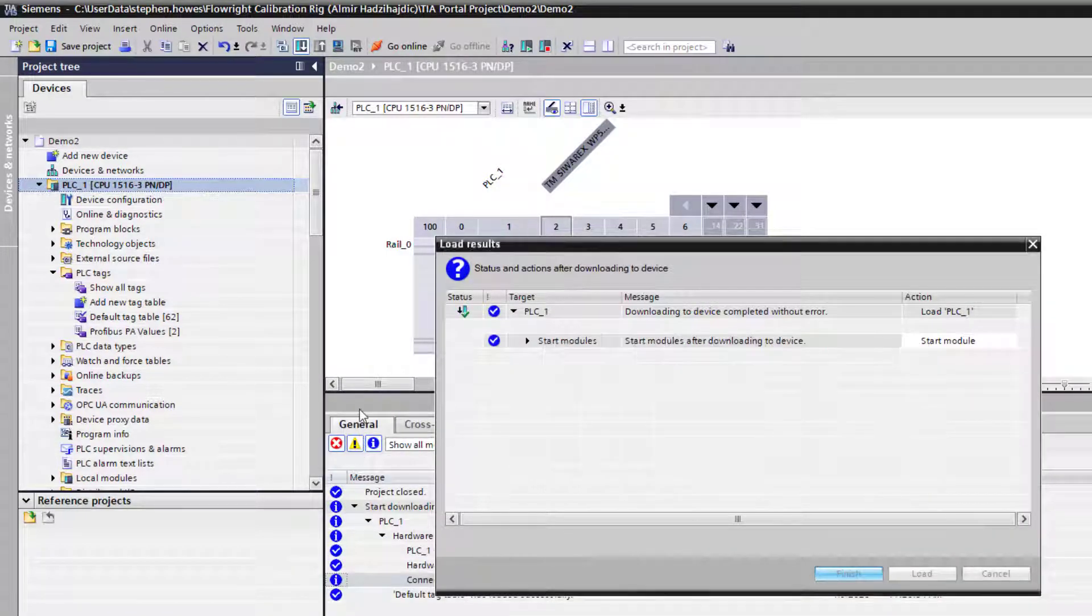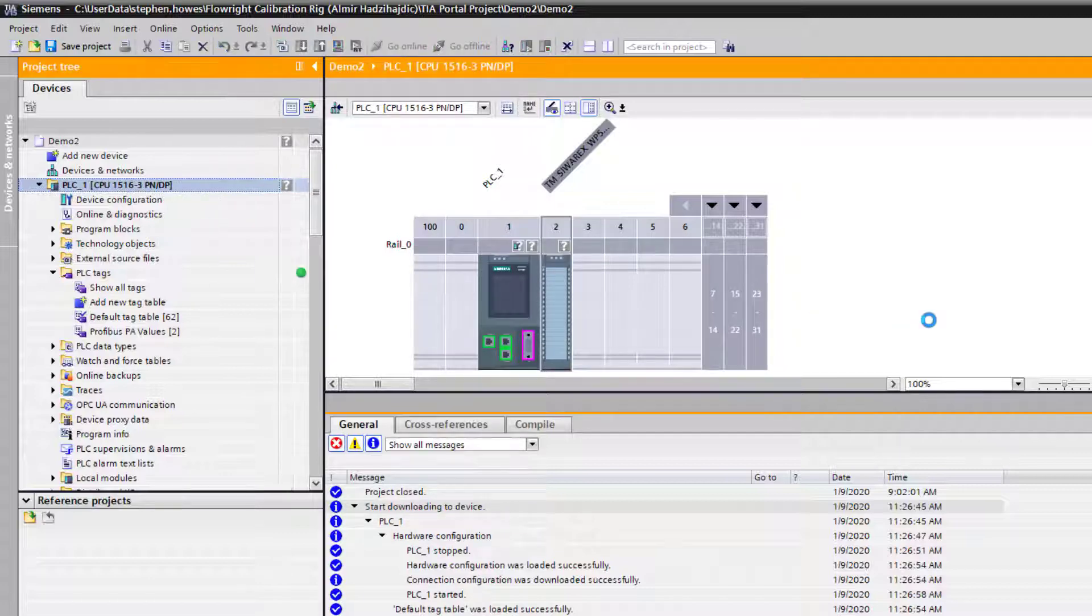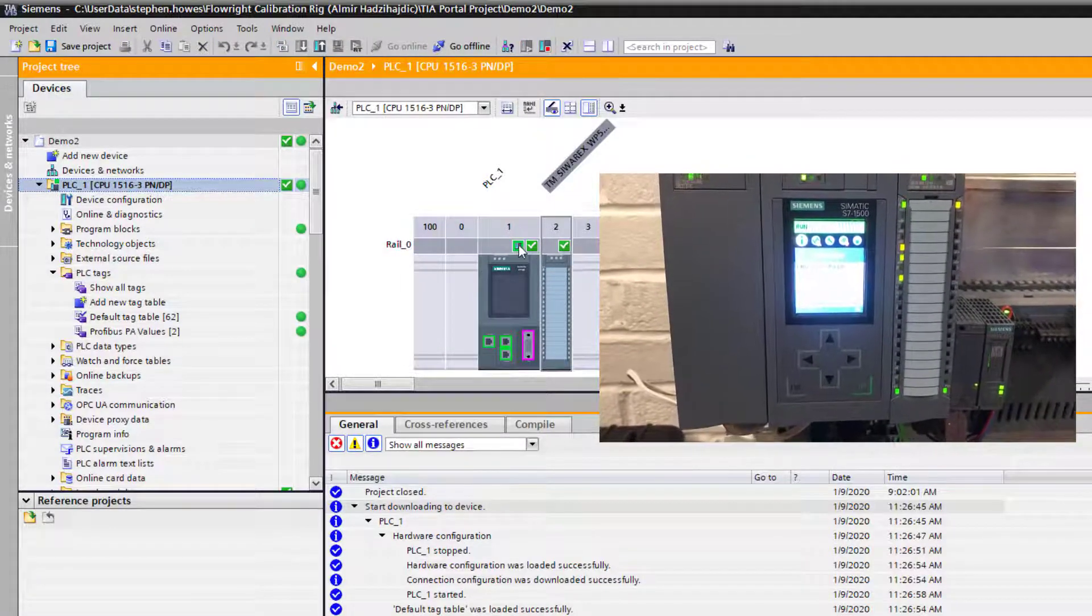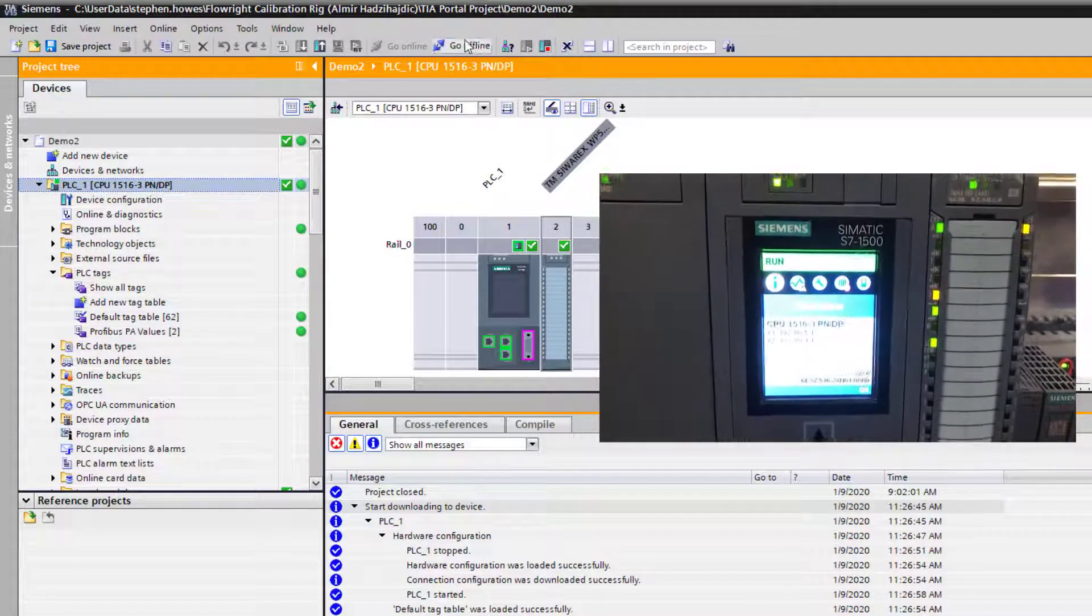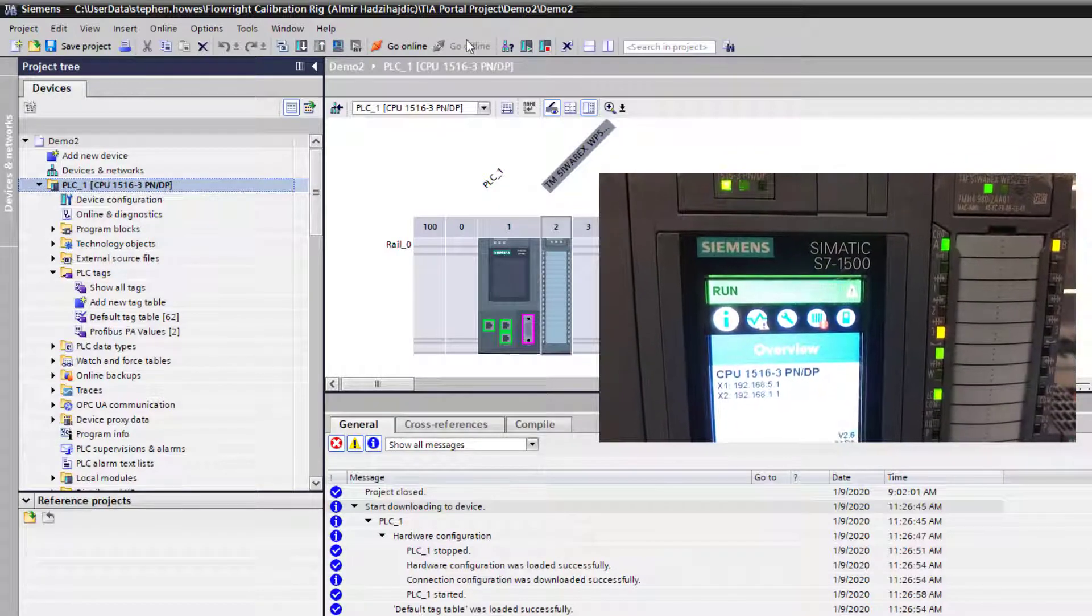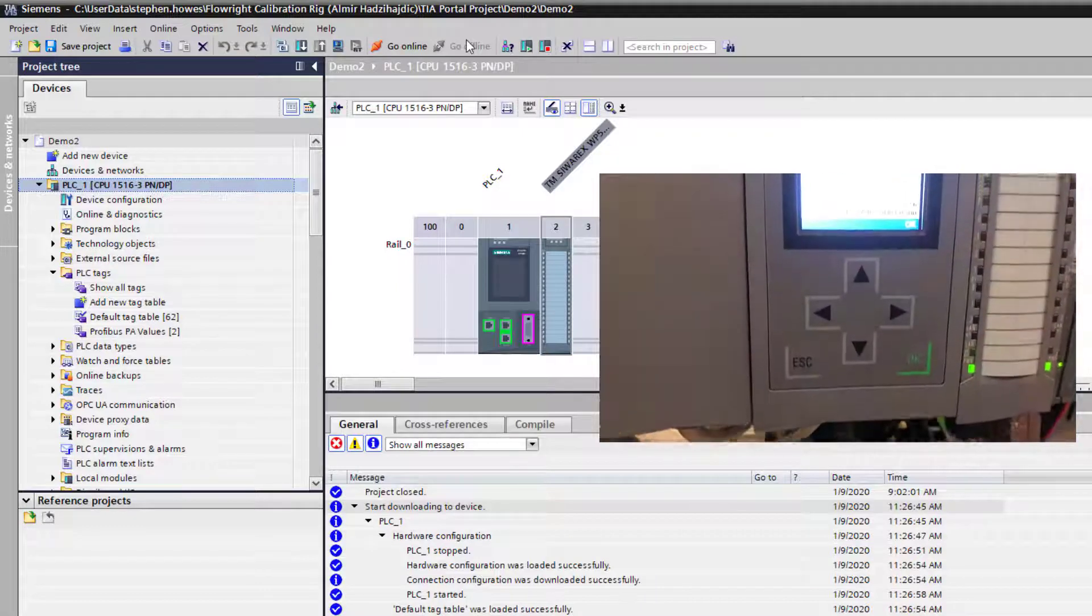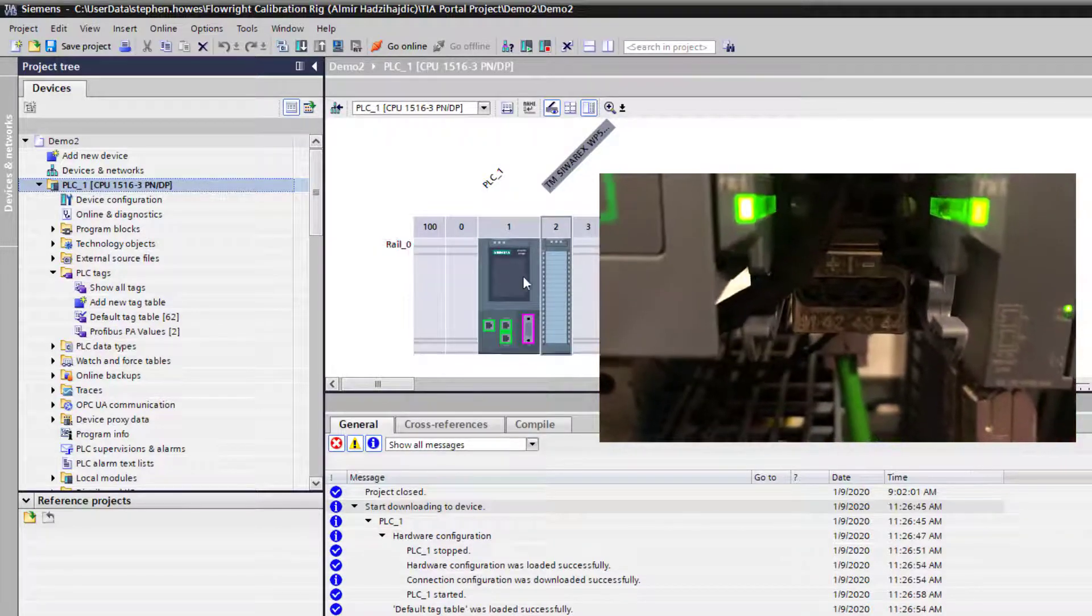We'll just make sure that the card can be seen by going online. There we have it, there's my card. PLC's in run, I can see both of my cards. It is important to note that you will need to wire 24 volts onto the card for it to appear as okay in your project, otherwise it will say device not detected in the diagnostics.